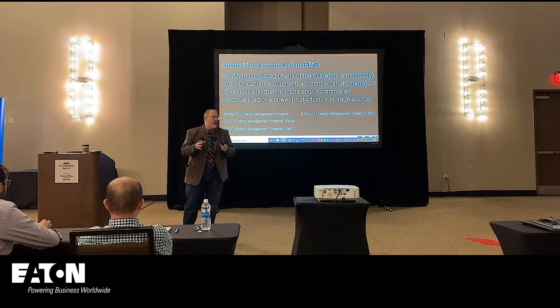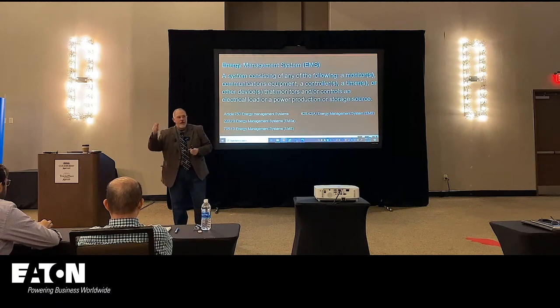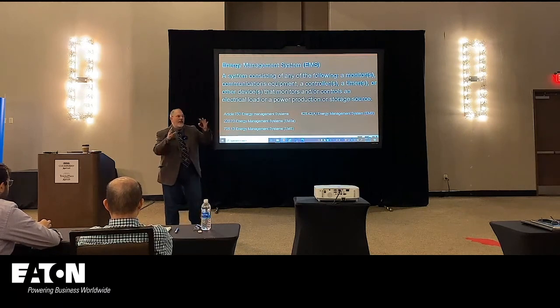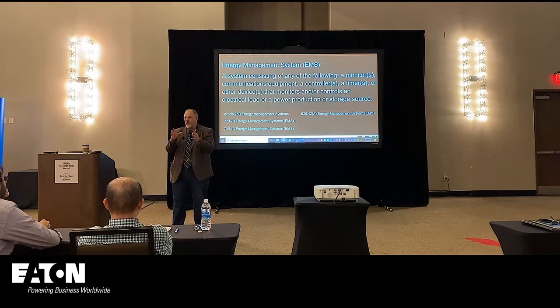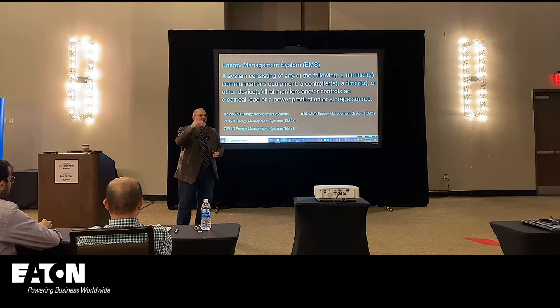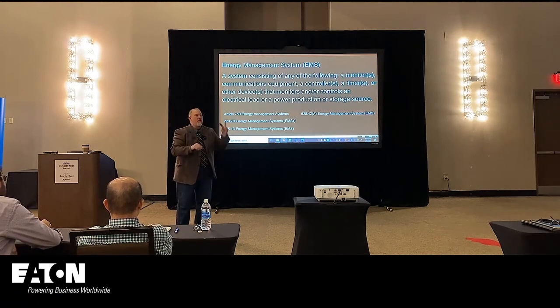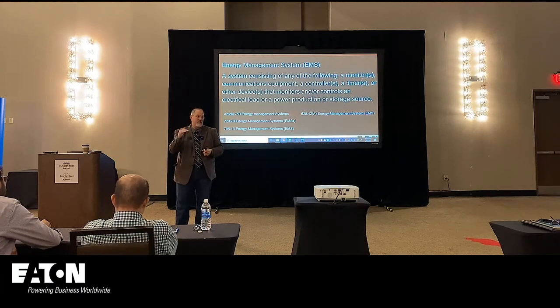So in the photovoltaic world, in Article 705, any interconnected system, they're basically saying, look, if you have an energy management system and it limits the amount of energy that it can put into the system, then you can size your panel board based upon the set point of the energy management system.